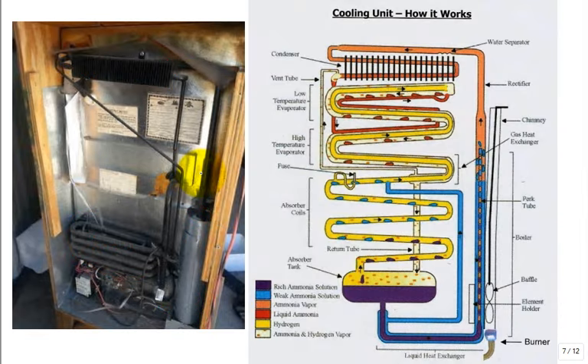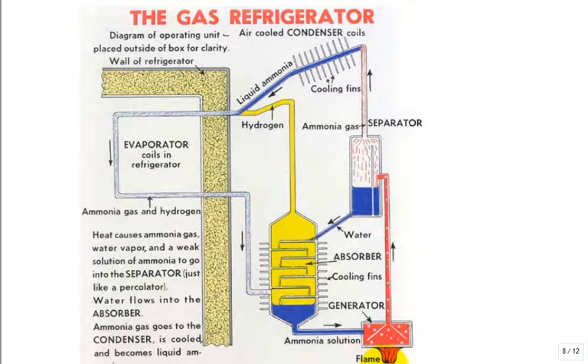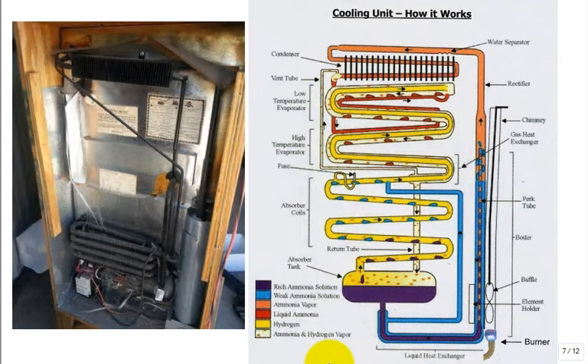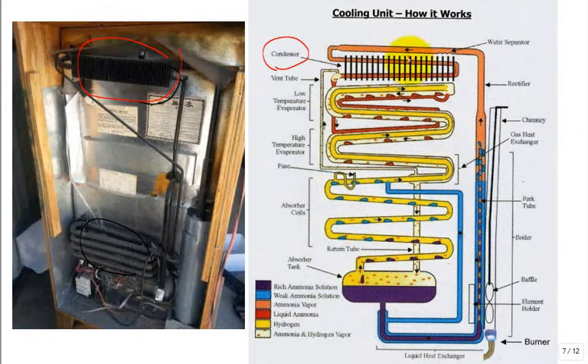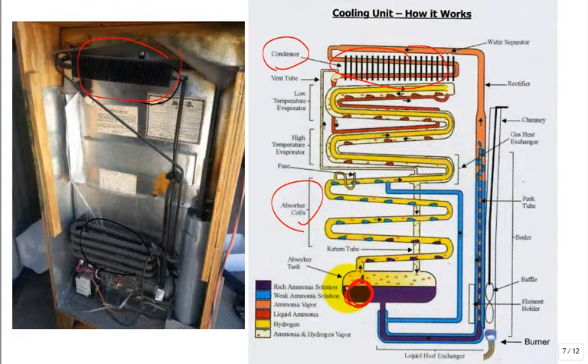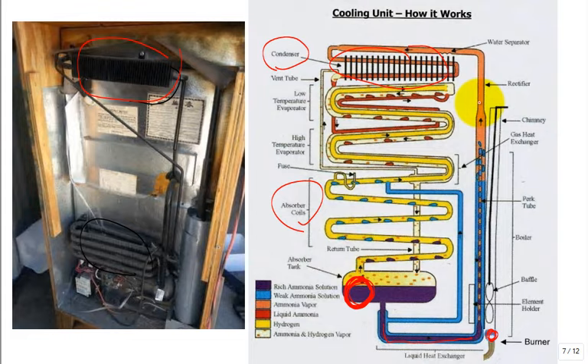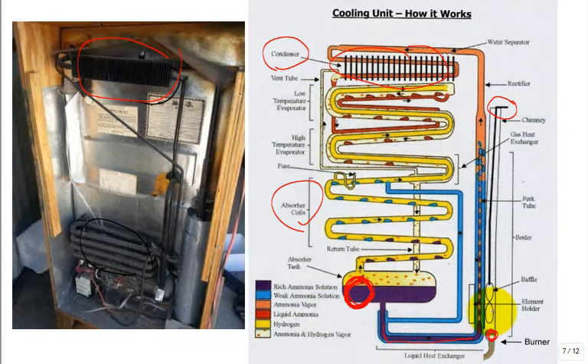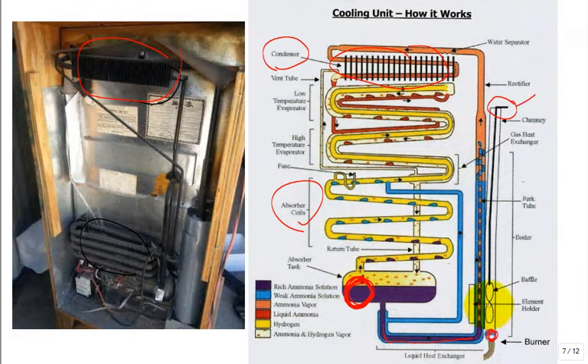You have to reject the heat off of the absorber and especially off of the condenser coil up here. You have to reject it off the condenser and you reject off this absorber coil. If you want a rich solution, do you want it to be hot or cold? Cold. You come in here, you then apply the burner and it percolates it up. Right here they're showing you a chimney with a little baffle to promote the convective heat transfer between the flame and the surface, and then the chimney to get rid of it safely.